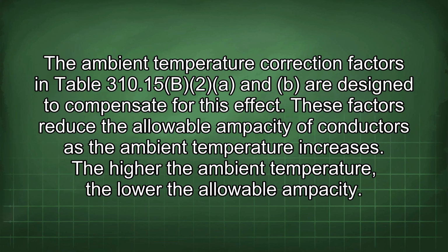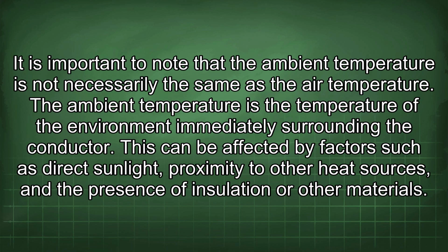These factors reduce the allowable ampacity of conductors as the ambient temperature increases. The higher the ambient temperature, the lower the allowable ampacity. It is important to note that the ambient temperature is not necessarily the same as the air temperature. The ambient temperature is the temperature of the environment immediately surrounding the conductor.